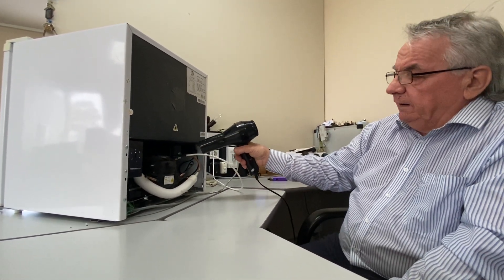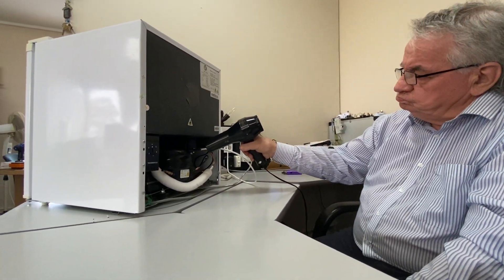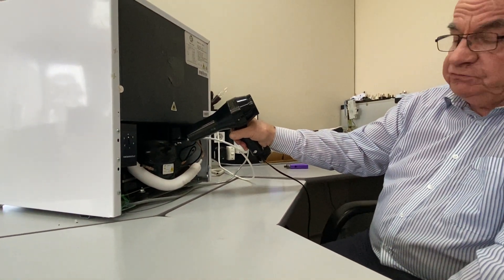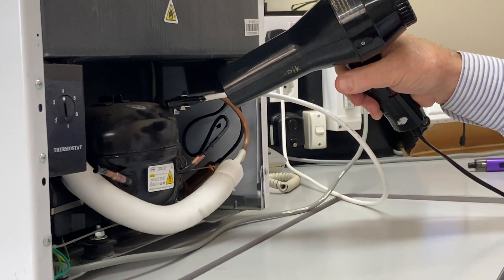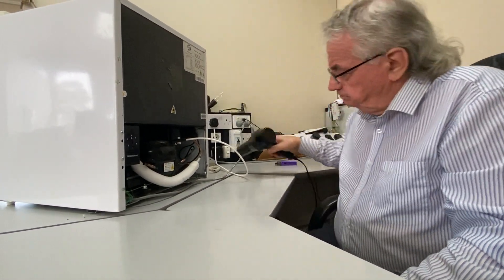Let's give it a try. This is simulating your compressor warming up, getting hotter. And it gets to 85 degrees C, which is far too hot for what it should be, but nothing like hot enough to create a fire. You can see it here. It says it all, doesn't it? The refrigerator — nothing is working now because the circuit's gone out.